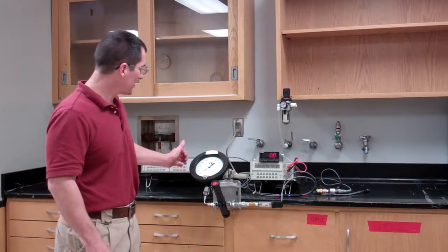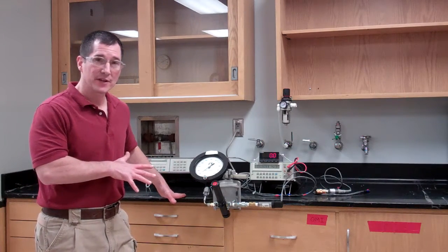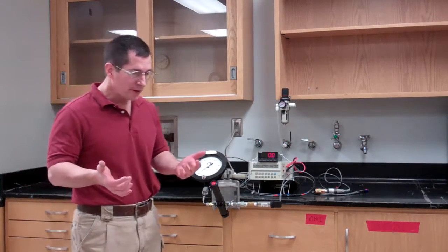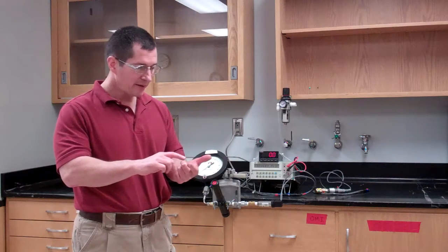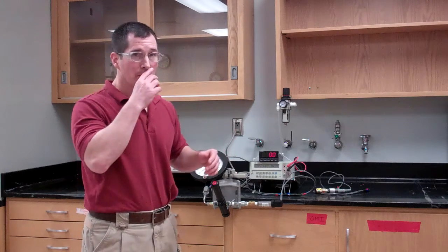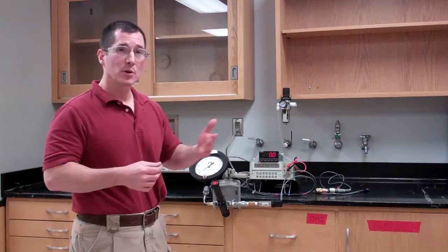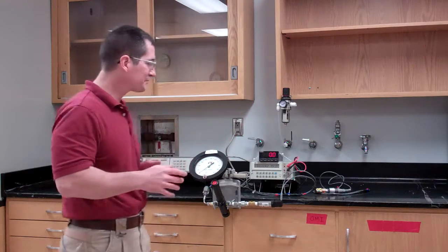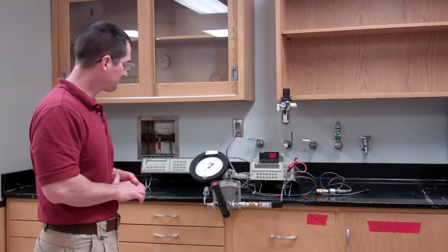Hello. This is experiment 710, pressure control, and this is going to be a calibration of the pressure transducer. So in your control system, you have an input measurement sensor that's measuring your process value, and then you have a controller and a final control element. So on this part of the experiment, we're looking at characterizing the input sensor. So we're going to calibrate it and check the calibration specifications to what the manufacturer says they should be, and see how good it really is.